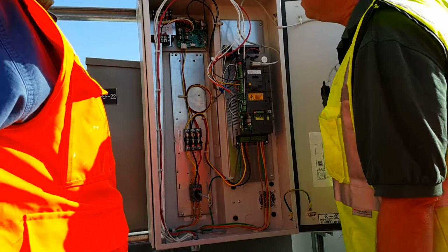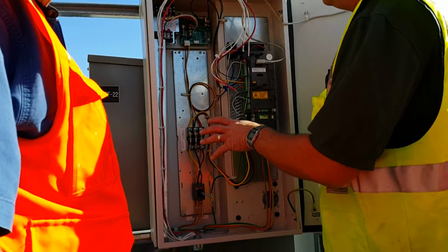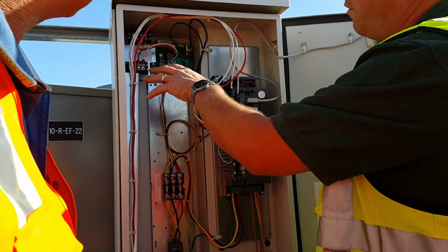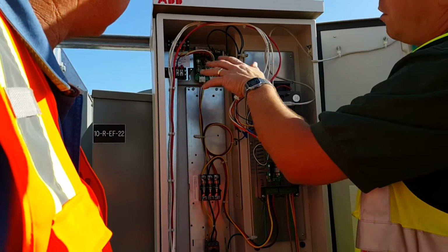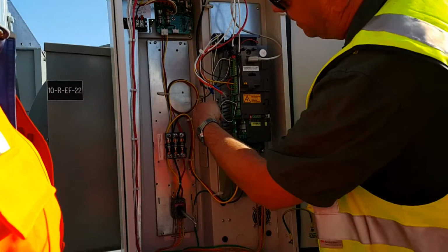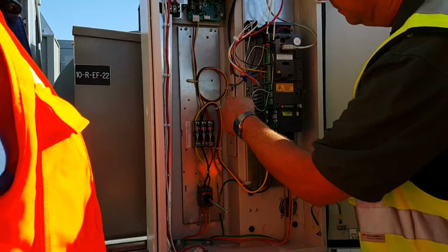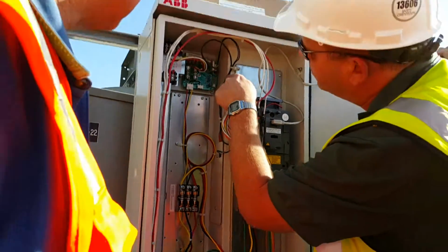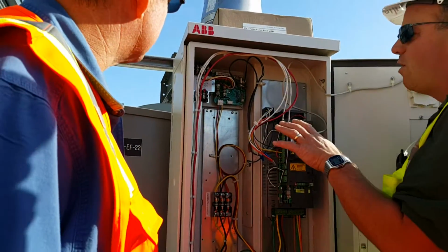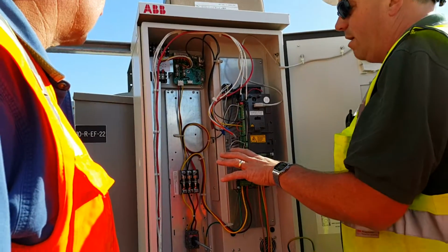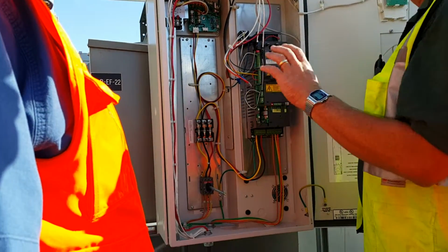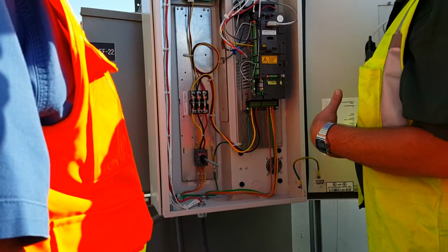Wrong. Couple things here, just so you know what all the components are. That's your 110 control transformer. That transformer, all it's doing is taking the 110 for this heater circuit right here. There's a heater you see sandwiched in between here that runs off of this board. So if it gets cold out here, especially if it's not running, it'll bring the heater on to keep condensation from building up inside the cabinet.